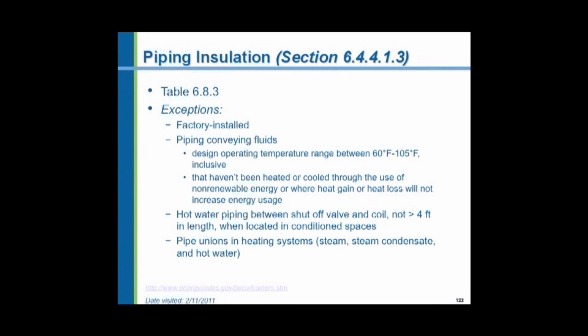It says hot water piping between the shutoff valve and the coil, not greater than 4 feet in length when located in conditioned spaces. Basically, if you have difficulties insulating things because of valves and controls, unions, relief valves, whatever that might be close to heating or cooling coils, you need not insulate that little bit of piping. And they say pipe unions in heating systems. Pipe unions are used by the service person. If he has to remove the boiler, the coil, the pump, whatever, he has to find a place where he can separate the piping. And if you insulate over the pipe union, he can't find it. He doesn't know where the union is, or even if there is a pipe union. So they're saying, please don't insulate over them.